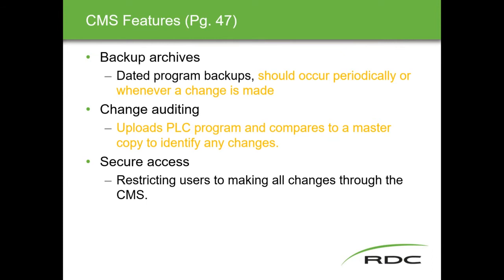Change auditing, like I said earlier, uploads the PLC program and compares it to a master copy to identify any changes. So again, it's easier to do in software than it is to actually open up the programs, put them side by side, and visually do it yourself. Secure access is provided by change management systems in terms of user access privileges and authorizations, restricting users to make all changes through the CMS. So that keeps everybody out of the program and only allows changes from one particular place.